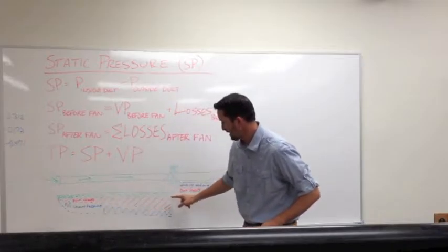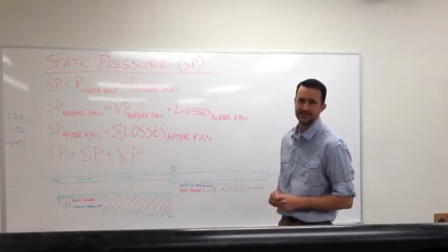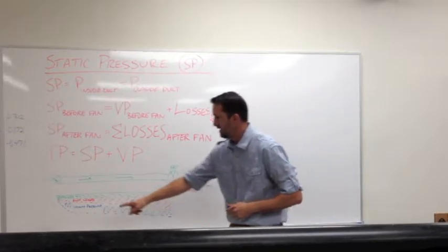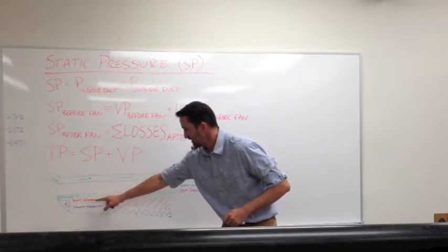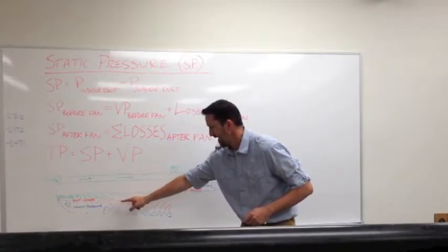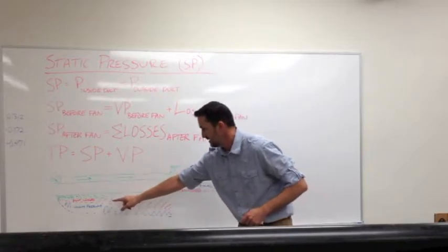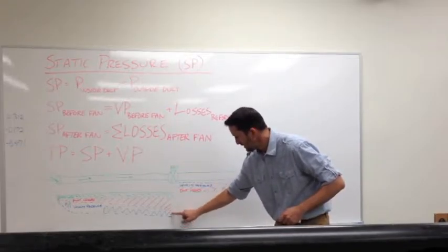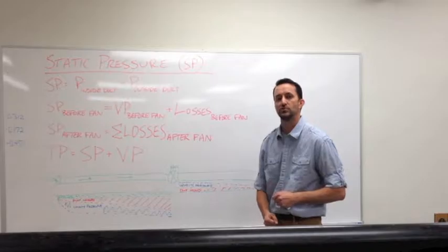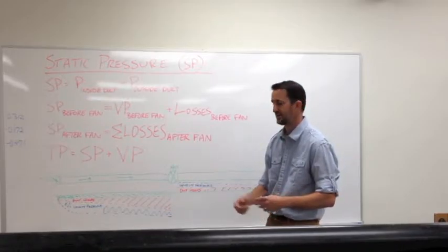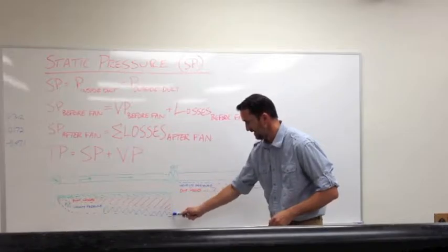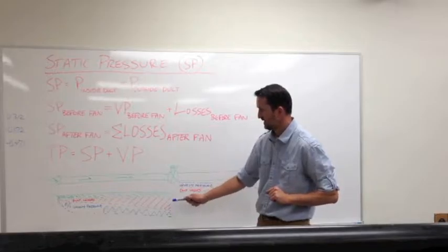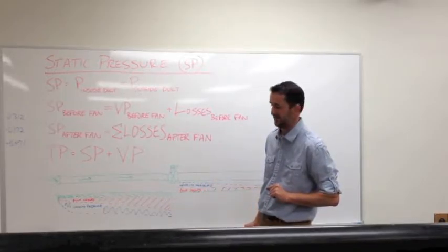Now the red wedge-shaped section here represents duct losses, okay? Friction against the duct that the fan has to overcome. There's none initially, but that accumulates and adds up, okay? So we're adding that pressure as it moves along the duct. The pressure accumulates until you get to the fan, and you have this total pressure that the fan blades now have to move and press against in order to get the air to move. And it's in the negative direction. And we'll measure that here briefly to show you that. Okay? So static pressure is negative on the upstream side of the fan.